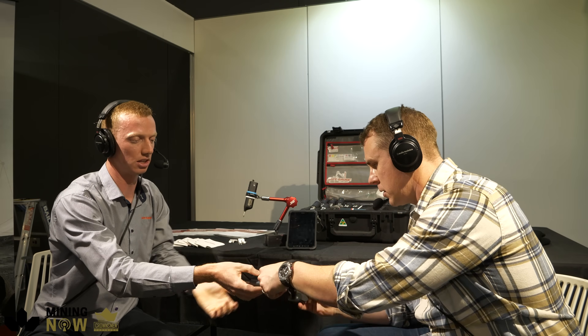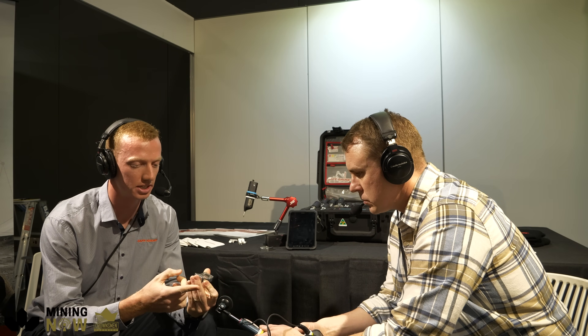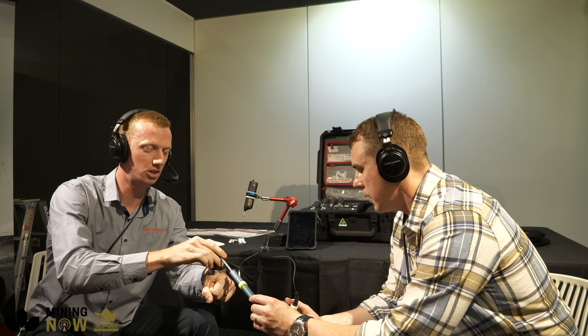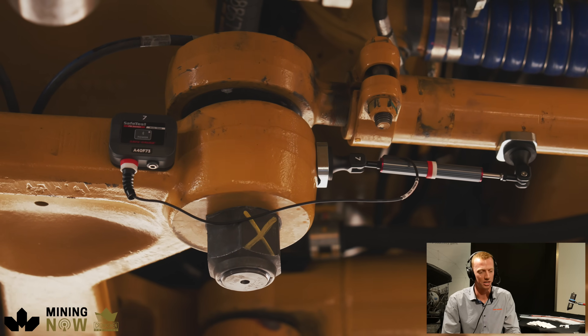The team asked: what's a different way of measuring it? The push rod is fairly lightweight, so it's still magnetic but much more manageable. They also added v-blocks based on customer feedback from the first prototype. When they went out to site with flat magnets, technicians needed to mount them to curved surfaces — a flat magnet on a curved surface wobbles around. Engineer Josh designed the v-block so that when it's on a curved surface it sits solid, giving a really secure location for an accurate measurement.